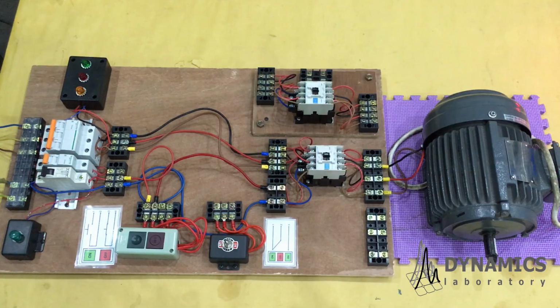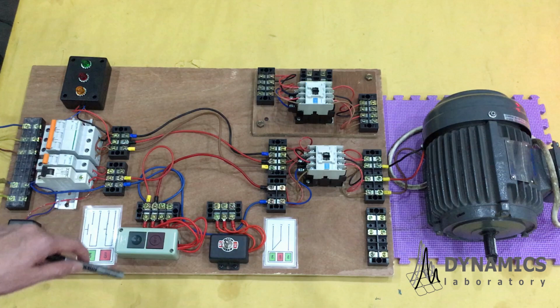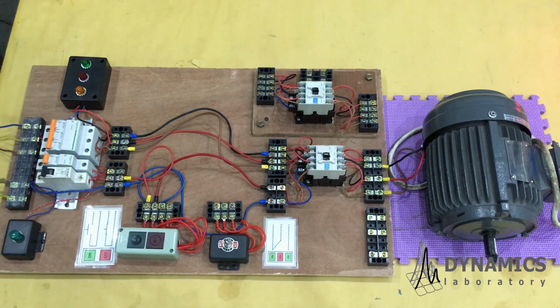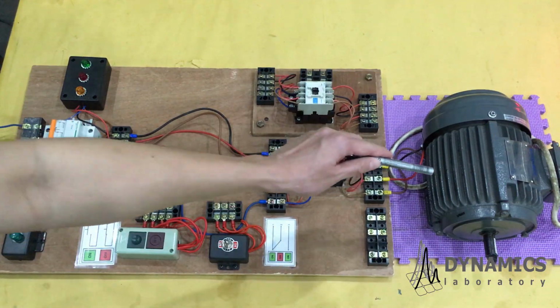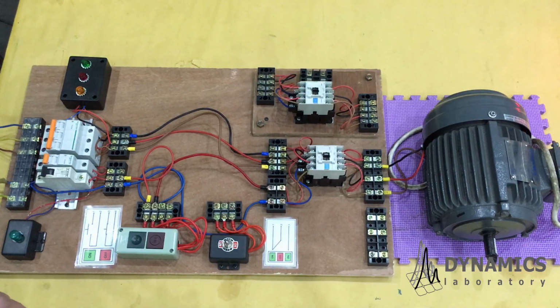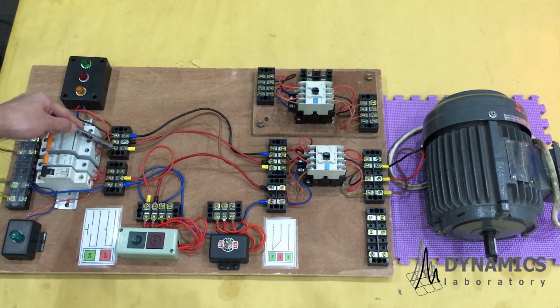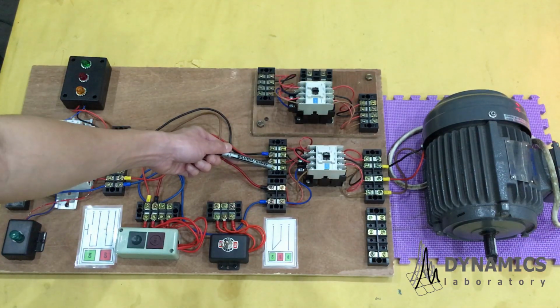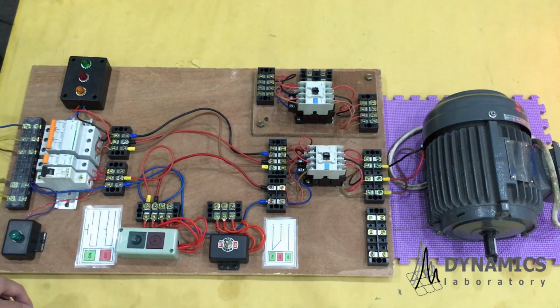Third load circuit, we will utilize three-phase AC induction motor and we will use push button control circuit. Let's see the load circuit. Actually, it's quite simple, as I have already explained before. Three-phase AC motor will have three coils, U, V, and W. And each coil should get different voltage line. That's why from the three-phase circuit breaker, you see R, S, and T voltage line directly connect to the contactor in here. Terminal 1, terminal 3, and terminal 5. That's why when the contactor is turned on, each coil will get different voltage line. That's how we run the three-phase AC motor.